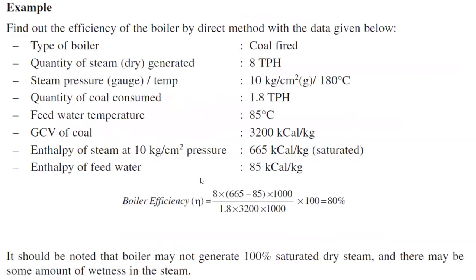Looking at an example problem to find the efficiency of a boiler by the direct method: the boiler is coal-fired, quantity of dry steam generated is 8 tons/hr, steam pressure is 10 kgf/cm² at 180°C, quantity of coal consumed is 1.8 tons/hr, feed water temperature is 85°C, gross calorific value of coal is 3200 kcal/kg, enthalpy of steam at 10 kgf/cm² is 665 kcal/kg, and enthalpy of feed water is 85 kcal/kg.